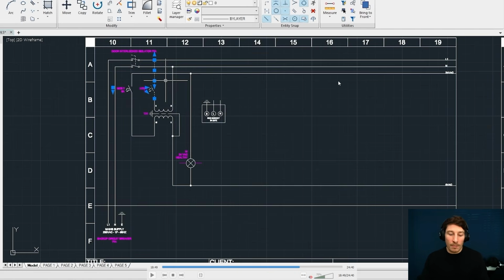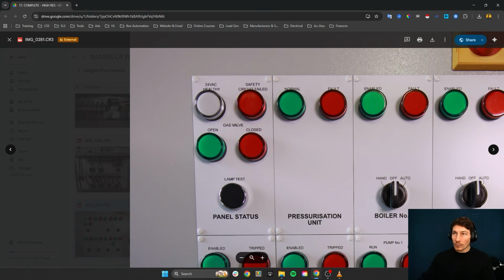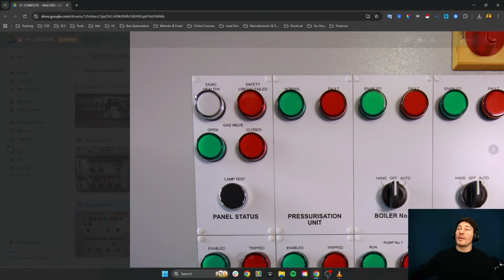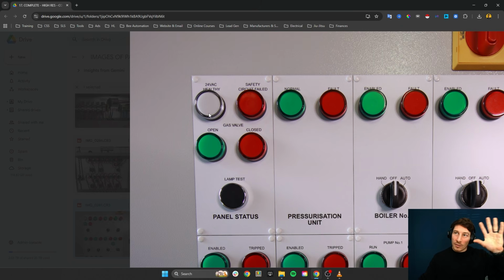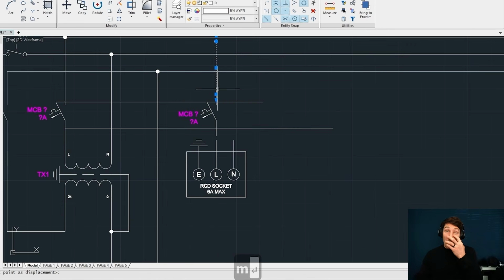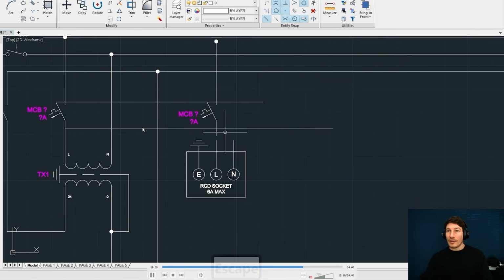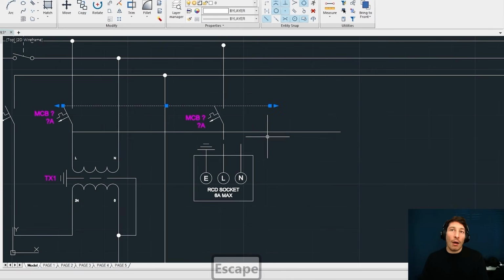So that's kind of just a silly example of how you would think through fault finding something like this, and why that's helpful, because we can just visually see, looking at the panel, oh, there's something. No wonder things aren't working. We haven't got 24 volt AC for our control circuit. Okay, well, why haven't we? That straight away takes us roughly to the right place to start looking, and then through a process of elimination, through logically breaking down the system, if we understand the designs, we can then work out where that issue lies, basically.